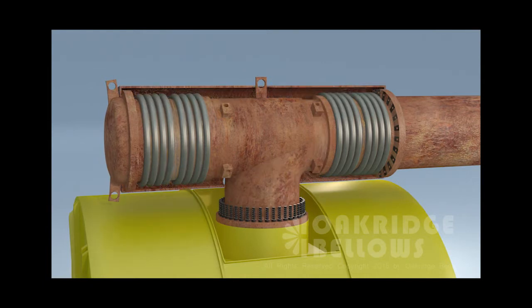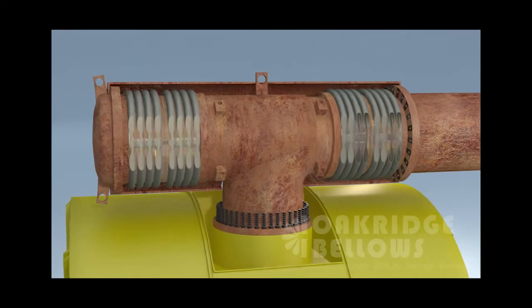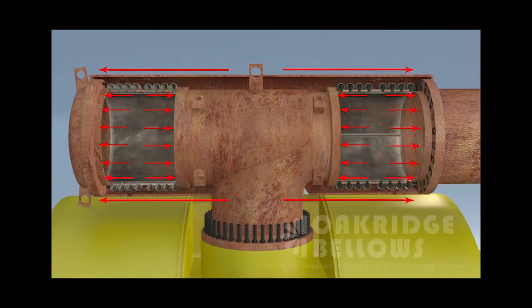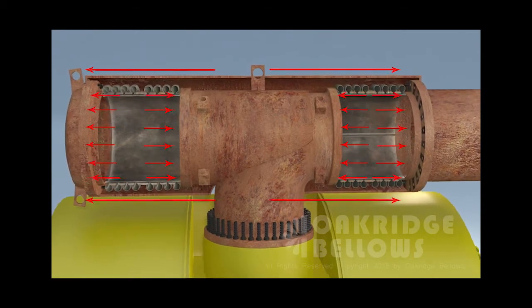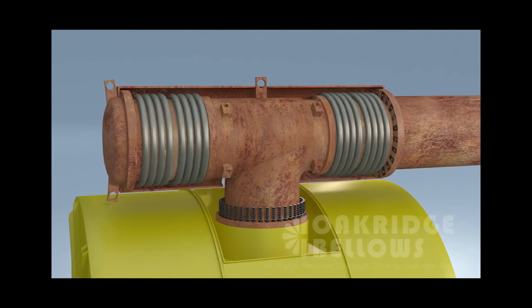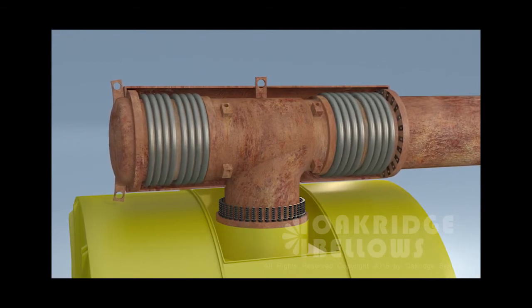Put the cover back on, and now when we pressurize it those forces are balanced. Each bellows is wanting to extend, the covers not letting it do it. But now that T section is free to move back and forth. That's how our pressure balance works.